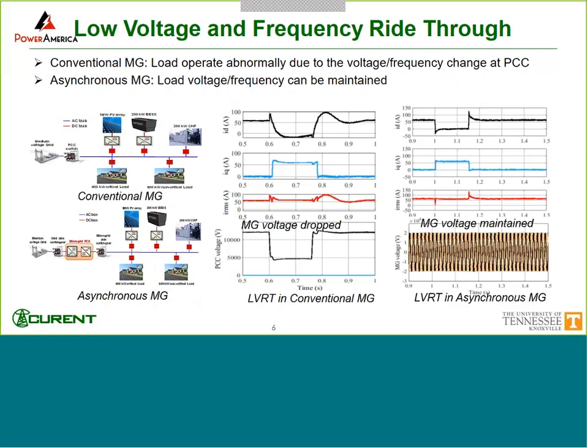This is an example, and we have some simulation work just to show. This is an example of low voltage and low frequency ride-through, and low voltage ride-through in particular, conventional microgrid versus the asynchronous microgrid. And this side shows the low voltage ride-through in the conventional microgrid, and this side shows the corresponding one in the asynchronous microgrid. And as you can compare the voltage, of course, the asynchronous microgrid is isolated from the conventional grid through this PCS, so the voltage magnitude, at least in this case, is very well maintained. So you will not expect a voltage drop as shown on the left-hand side.